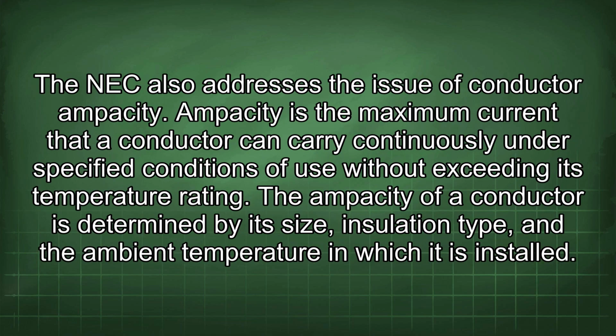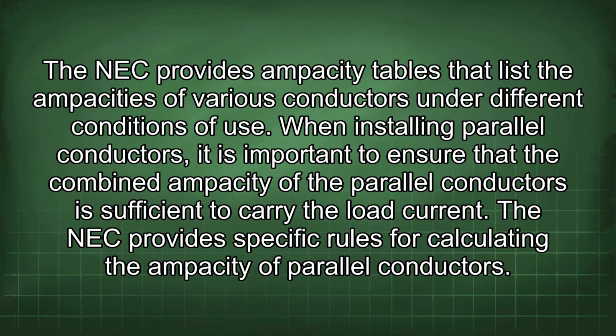The NEC also addresses the issue of conductor ampacity. Ampacity is the maximum current that a conductor can carry continuously under specified conditions of use without exceeding its temperature rating. The ampacity of a conductor is determined by its size, insulation type, and the ambient temperature in which it is installed. The NEC provides ampacity tables that list the ampacities of various conductors under different conditions of use. When installing parallel conductors, it is important to ensure that the combined ampacity of the parallel conductors is sufficient to carry the load current. The NEC provides specific rules for calculating the ampacity of parallel conductors.